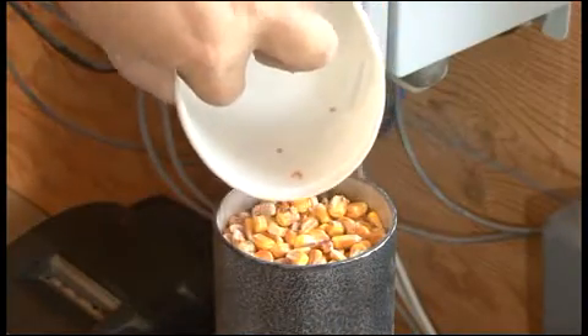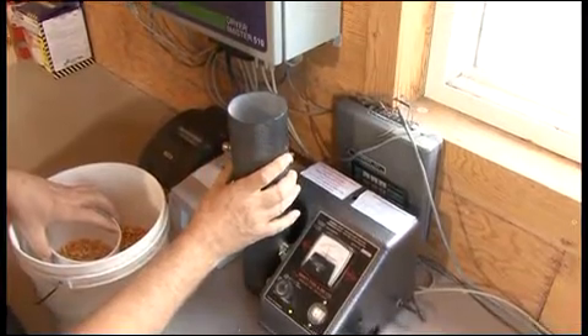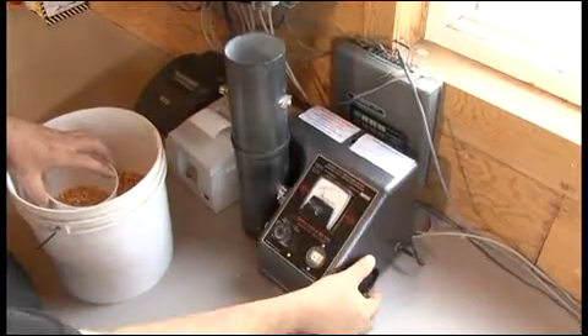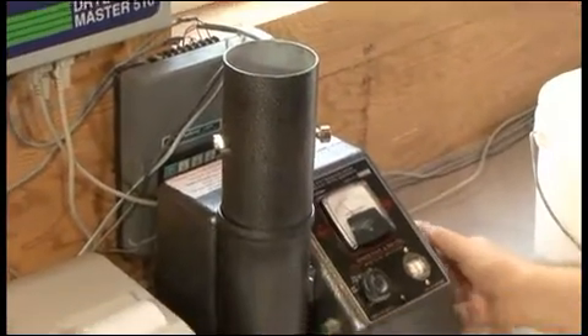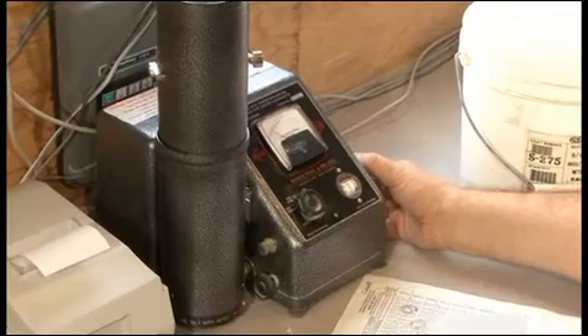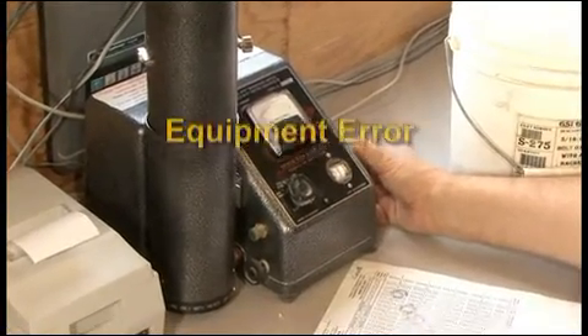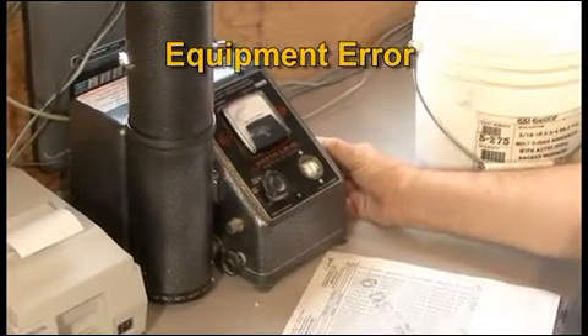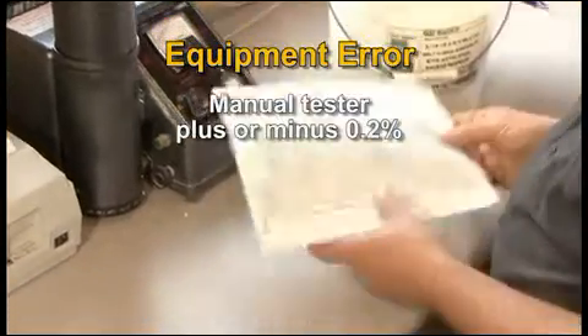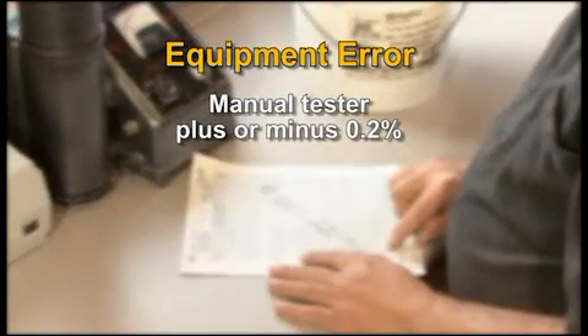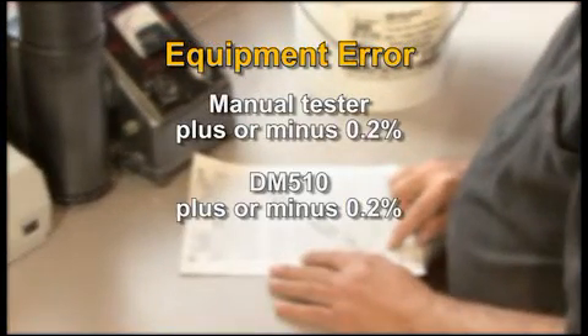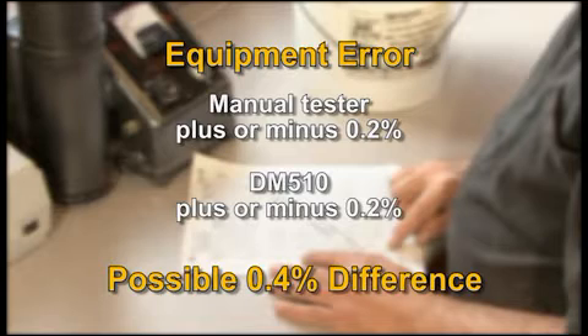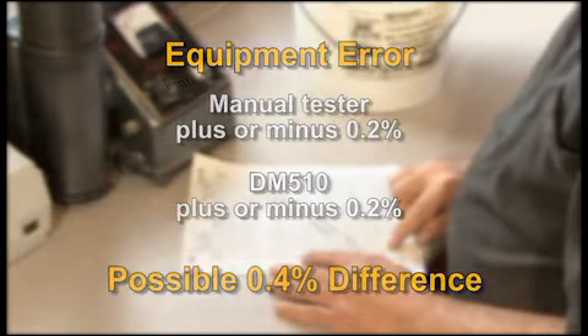If you take the first manual sample and put it in your benchtop sensor, you will get a moisture reading. Now, if you put the same sample back into the tester again, you might get a slightly different reading. This is called equipment error, and it occurs because most manual testers have a plus or minus 0.2% error range. The Dryer Master moisture sensors have a similar error of plus or minus 0.2%, so it is possible for the two sensors to read as much as 0.4% difference and still both be accurate.